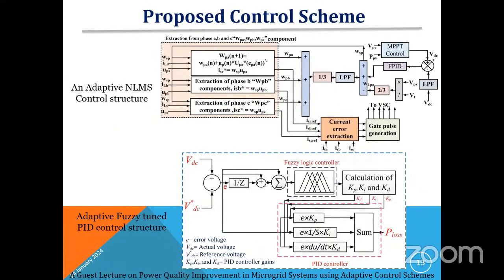These are the complete control structure of the proposed adaptive control scheme. These types of controls work based on the fundamental weight components from the grid load currents and grid voltages. In the first step, we have given load currents, because based on the load, the grid currents and grid voltage contain harmonics. So we give the load currents as input to the controller. The load currents have two types of components: one is the fundamental component, another is the harmonic component. The working principle of this type of controller is that it extracts the fundamental components from the load currents and gives the remaining harmonic components to the controller.